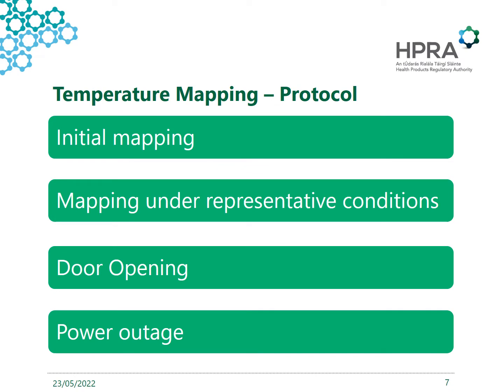The first step is to create the protocol to outline how the company intend to approach the study. You expect an initial mapping to be conducted, which involves the installation qualification and operational qualification. This should show that the storage area and equipment within is capable of maintaining the required conditions. It should also document the acceptance criteria, the proposed alarm limits and set points.